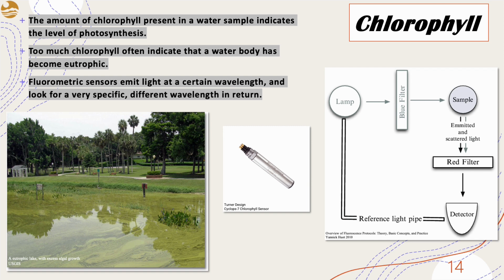But too much chlorophyll is often an indicator that the water body has become eutrophic. Eutrophic water looks unappealing, can produce taste and odor problems in drinking water treatment, and it can also cause death of fish when the photosynthetic organisms such as algae die and decay rapidly. The chlorophyll sensor on our data sonde is a fluorometric sensor. Fluorometric sensors emit light at a certain wavelength, and you look for a very specific different wavelength in return. If you shine a blue light at chlorophyll, the chlorophyll absorbs some of the blue light and then emits red light. More chlorophyll produces more red light. The magnitude of returned red light is relatable to the amount of chlorophyll present in the water sample.